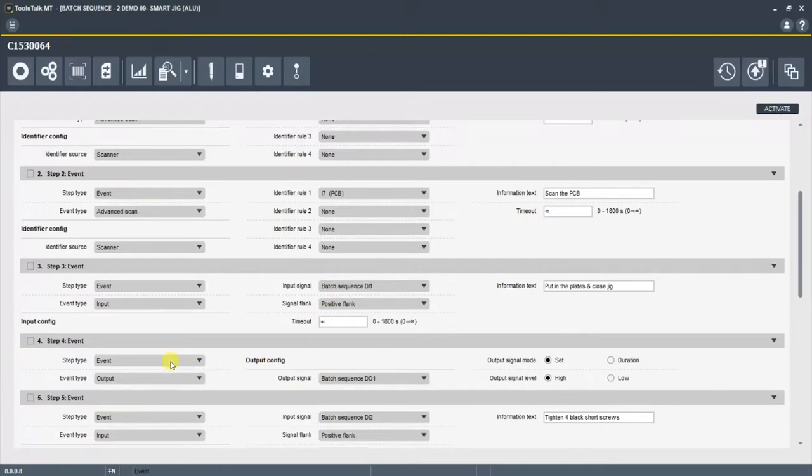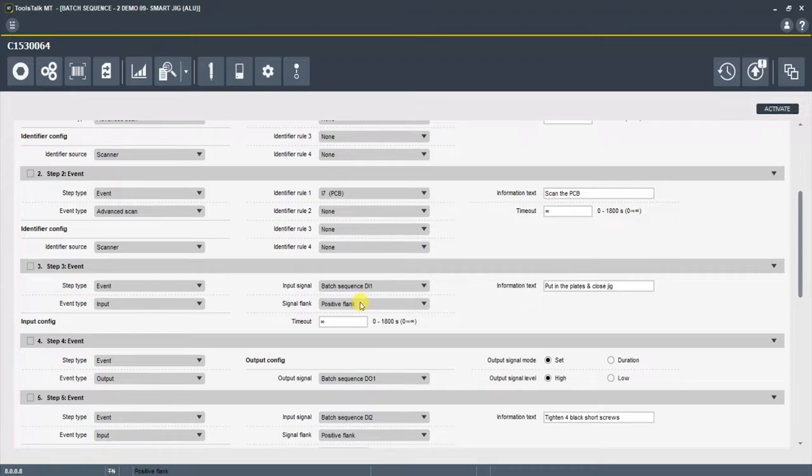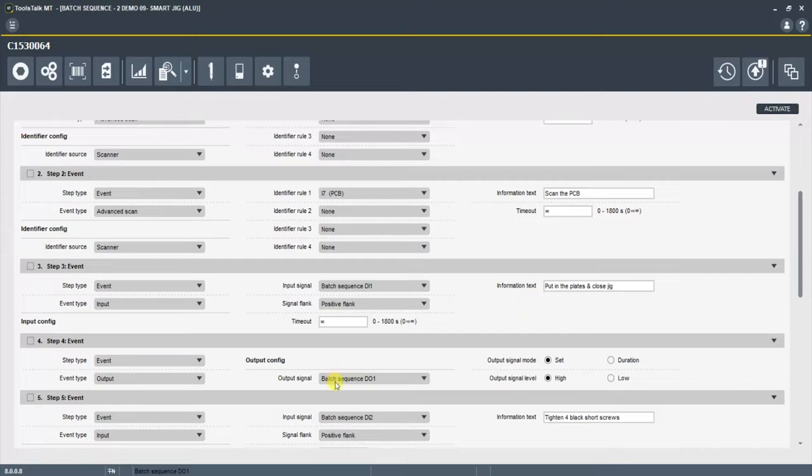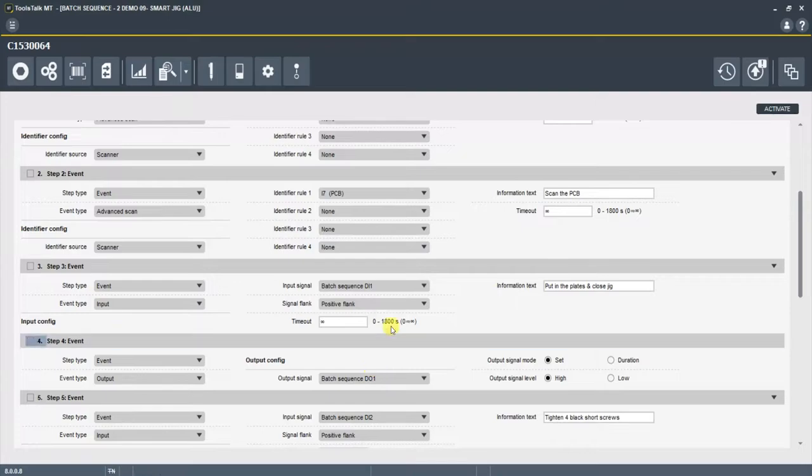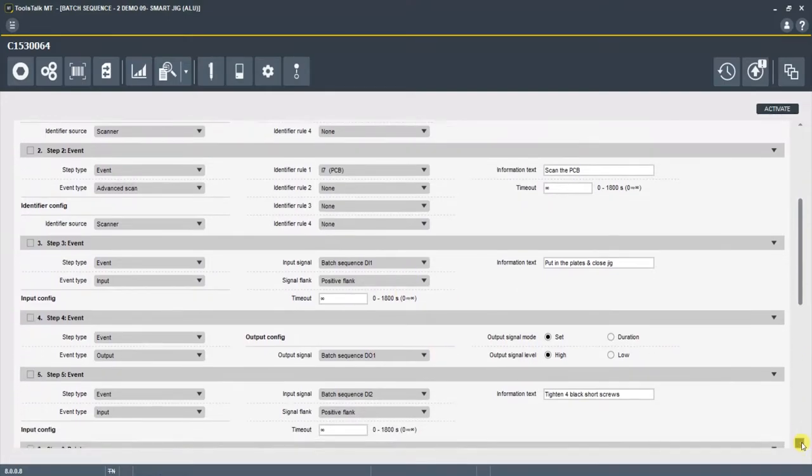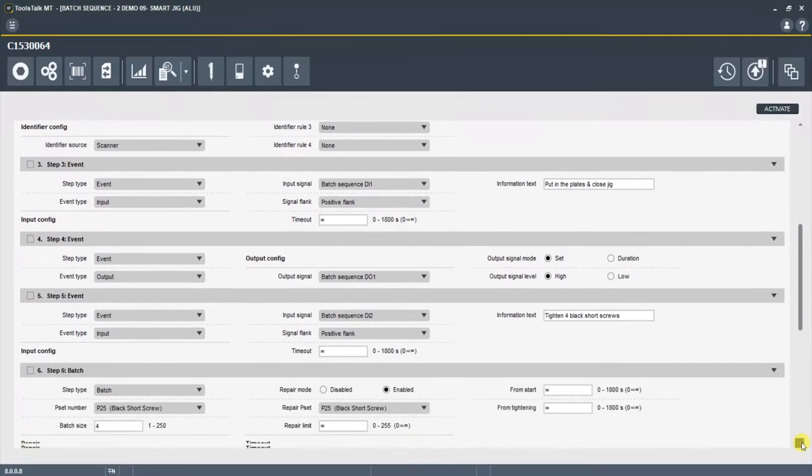It moved right through step four, which is an event step, which is an output step. So as soon as it saw this positive flank in step three, that the jig was closed, now I'm going to send a digital output. And we identified that output as digital output number one, which is an output we set up to lock the jig. So as soon as it was closed, it locked and moved through step four. And now we're on to step five.